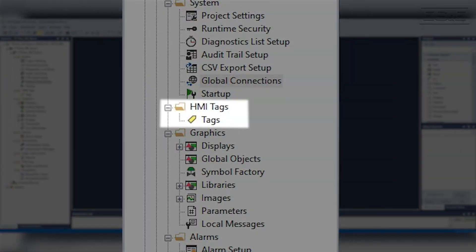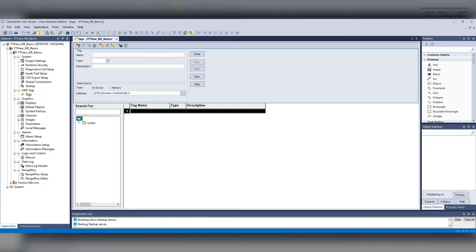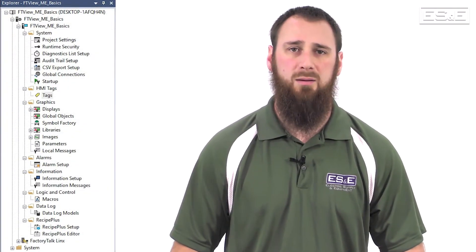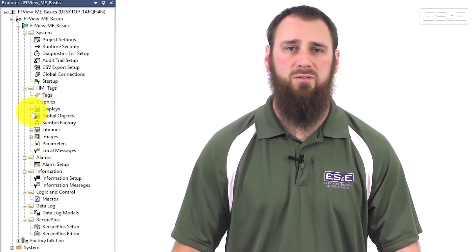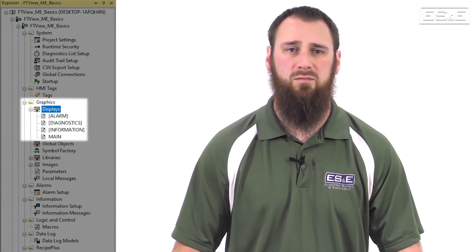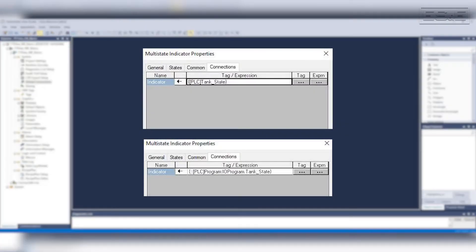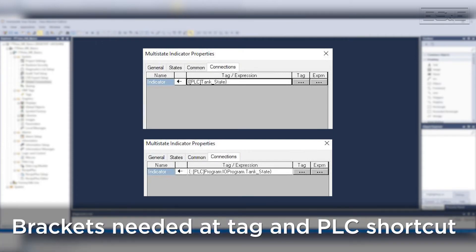The next area is the HMI Tag Folder. There are two different ways you can address PLC tags from the HMI. You can create HMI Tags, which allows you to import and export tags for bulk editing. HMI Tags take up some memory but speed up the process and allow graphics to have easily readable tags. The other option is Direct PLC Tag Referencing, which does not show up in your HMI Tag Folder. Instead, they are on each individual graphic display object, where you can go to the connections and tie those directly to a PLC tag name. The syntax gets a little different because you have to have brackets around the tag and the PLC shortcut topic. Both options work — it is just a preference of the person developing the application.